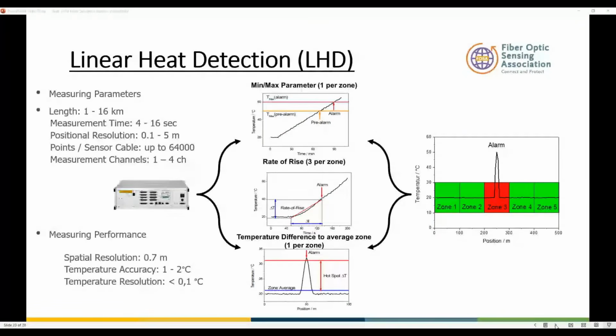Virtually, it's flexible. In the middle of this slide you essentially have three parameter outputs: minimum and maximum temperature, rate of rise, and temperature delta. You can architect a true Class A loop cable routing in case the cable is cut, giving you failover. This reduces false alarms and gives precise and accurate actuation of fire suppression systems.